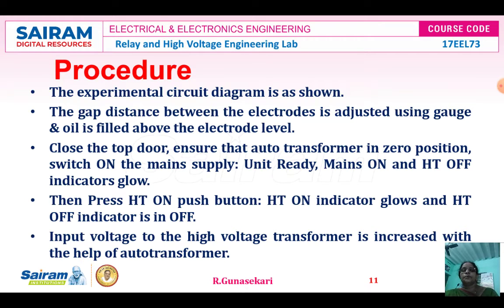Procedure. The experimental circuit is as shown in the figure. The gap distance between the electrodes is adjusted using gauge and oil is filled above the electrode level. Close the top door. Ensure that the auto transformer is in zero position. If the auto transformer is not in zero position, the unit ready indicator lamp never glows. That's why the auto transformer must be in zero position.